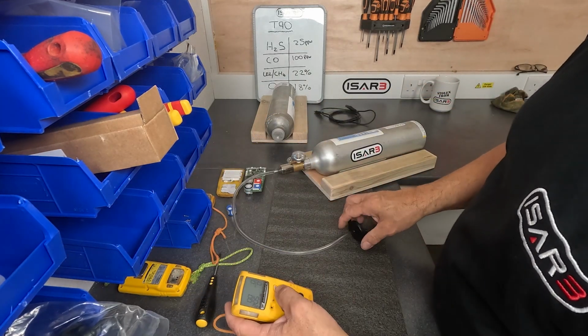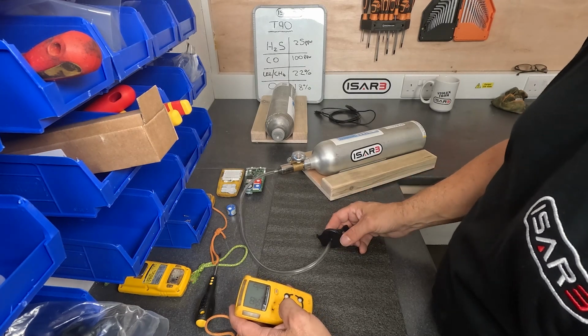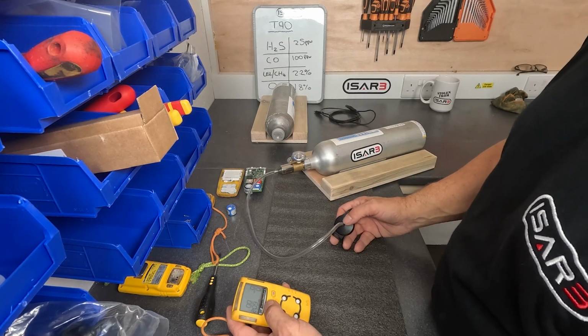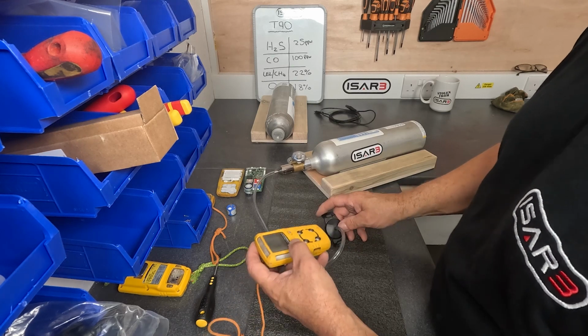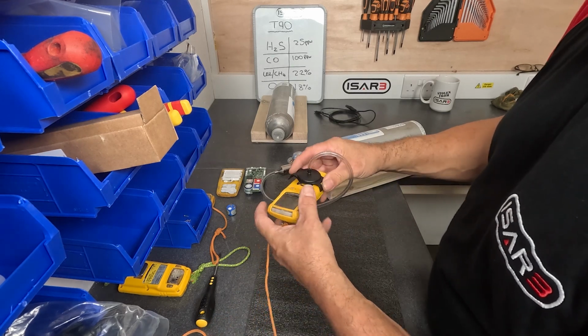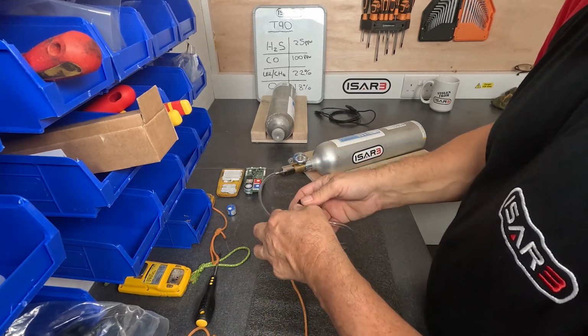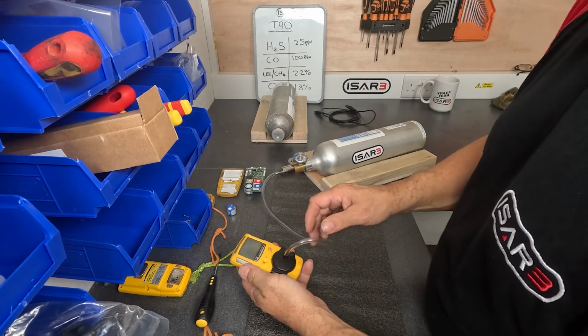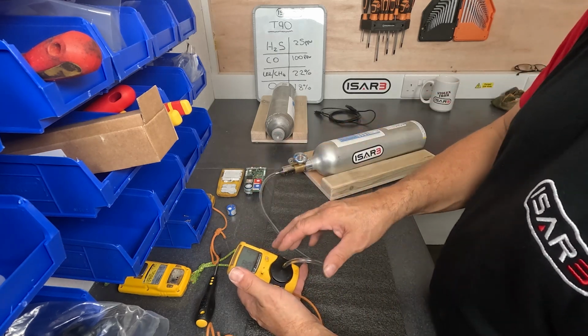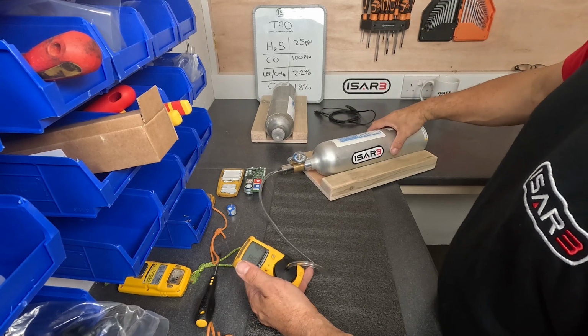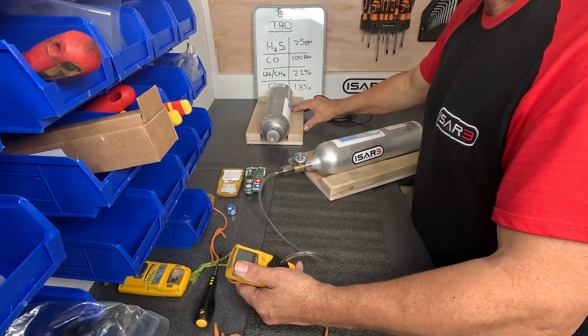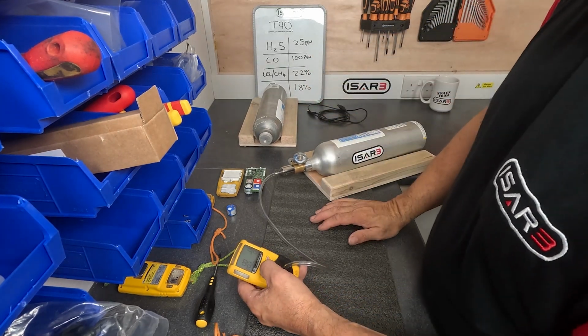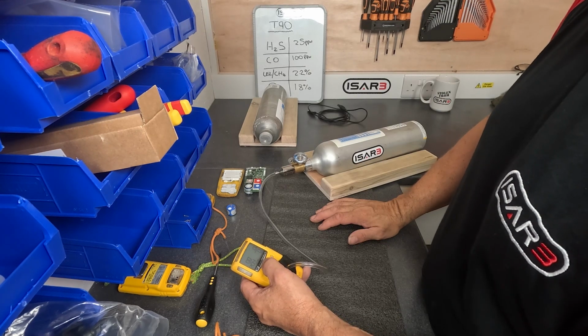Your gas detector would have been turned on outside in fresh air, and it wants a couple of minutes just to stabilize itself. And then it's just simply a question of plugging the shroud over the top of the gas detector so that when you show gas to it, it's going to flush all the sensors. Make sure you've got a copy of these numbers here somewhere, because you can do more than just basically test that the sensor is going to react.